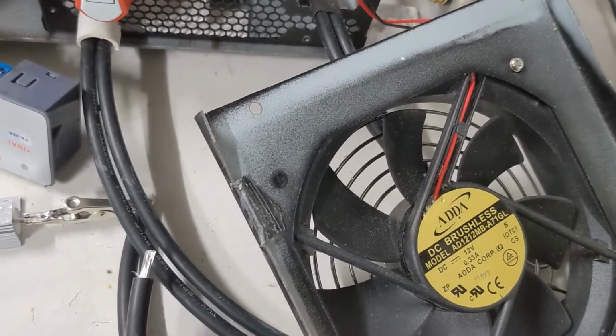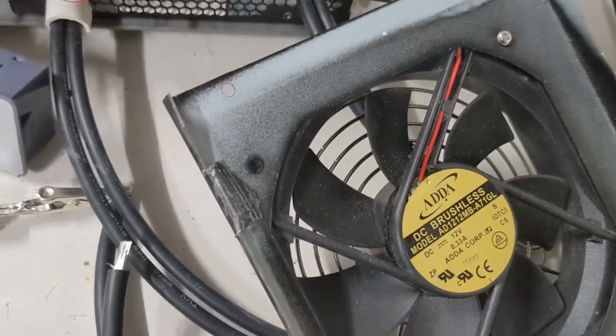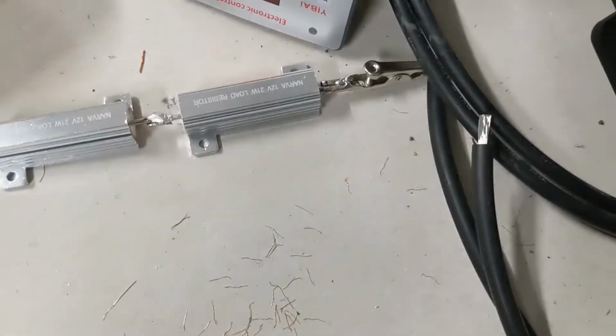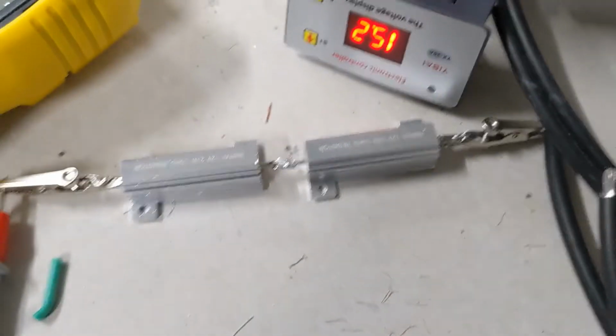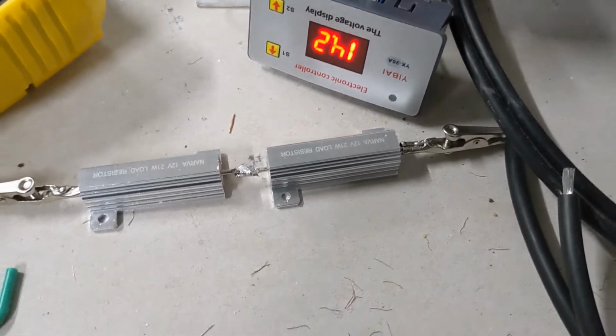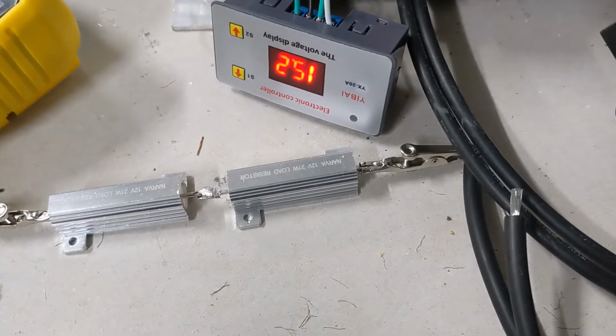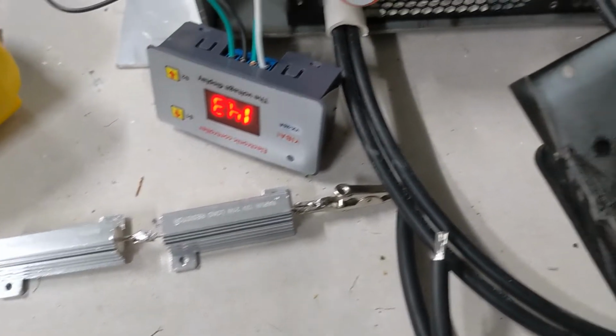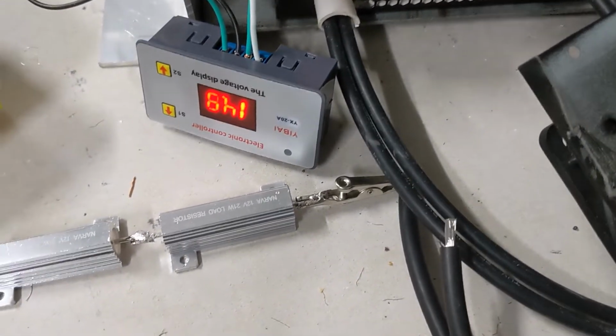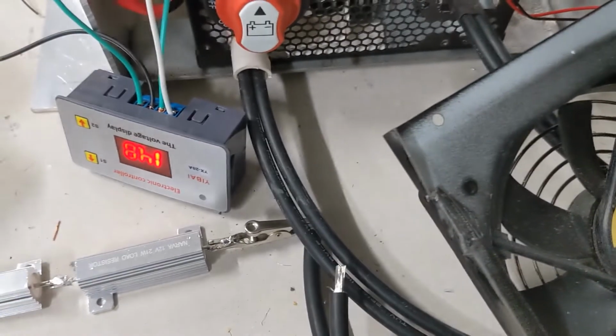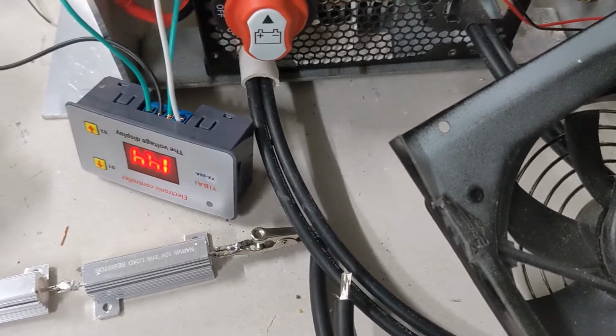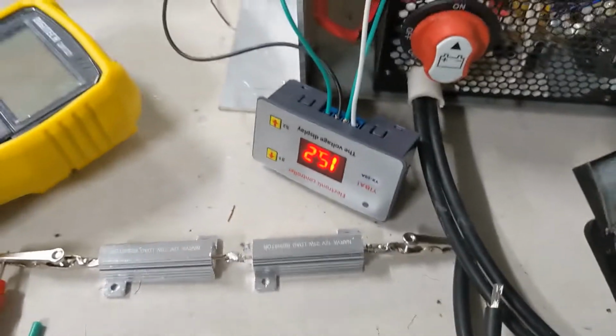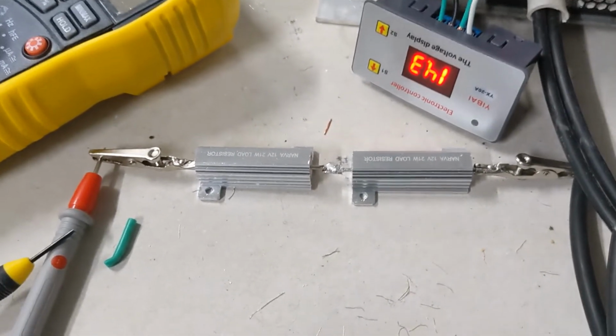We can see in principle it's definitely drawing what we asked. The problem is if the booster doesn't limit the current, then it's very likely the inverter will ask for as much power as it will give, and I suspect it will exceed our tolerances. So we really need the constant current function to be working correctly.